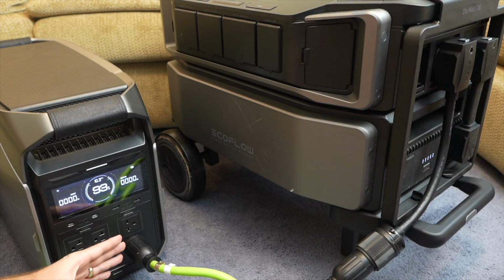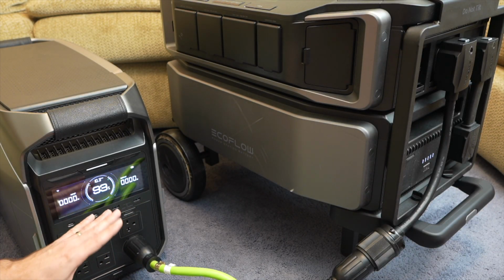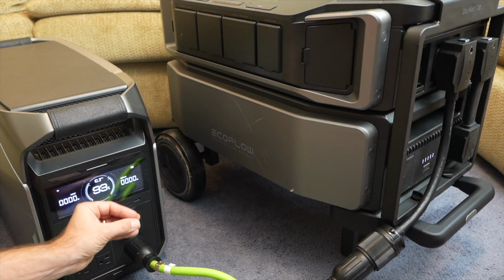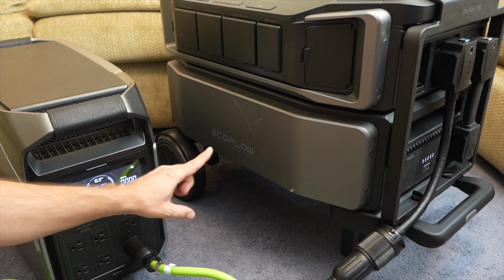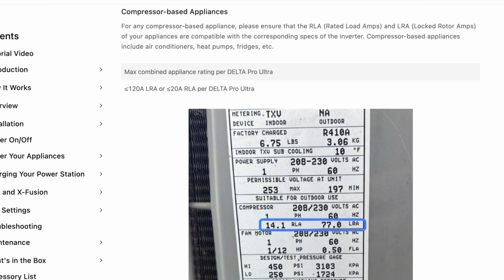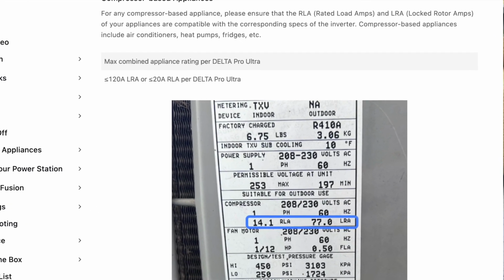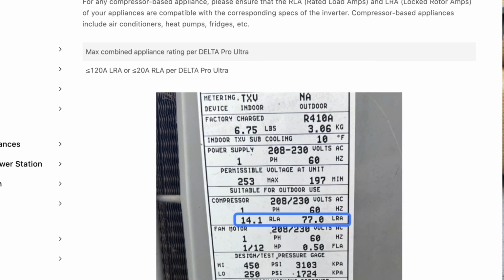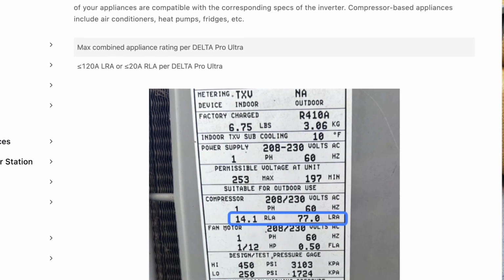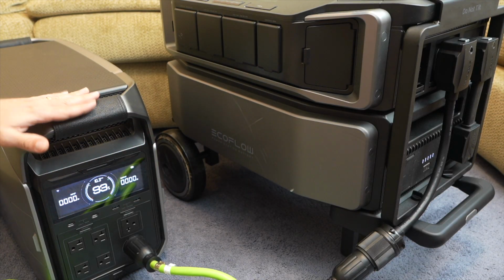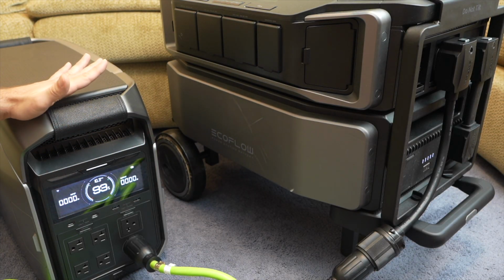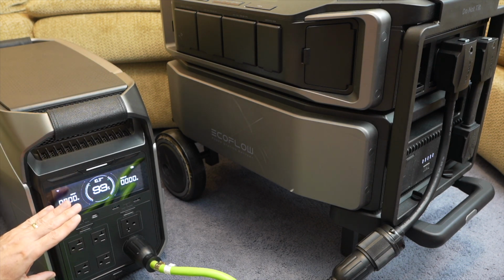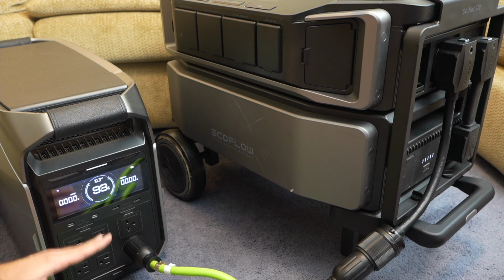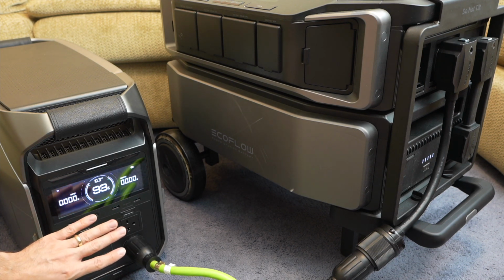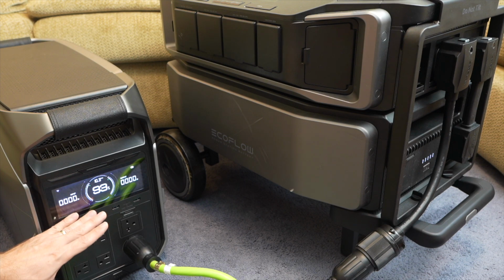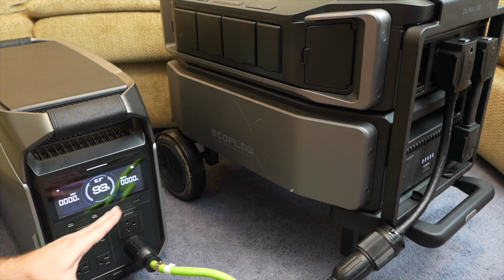Another thing to consider if you're going to use these to back up your house is the surge power, like an air conditioning unit, which requires a short burst of energy to get the compressor started. In the manual for the Ultra, they advise you to look at the sticker on your air conditioning unit and look for the LRA value. That stands for locked rotor amps. And if it's less than 120, the Ultra should be able to start it. Now, there isn't a corresponding one that I saw in the Delta Pro 3 manual, but if my math is correct, the LRA value would need to be 66 amps or less, because this has an 8,000 watt surge. And both of those numbers are assuming that nothing else is drawing power at the moment besides that air conditioning unit.